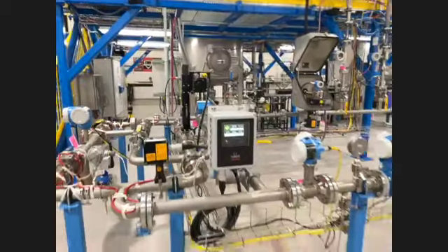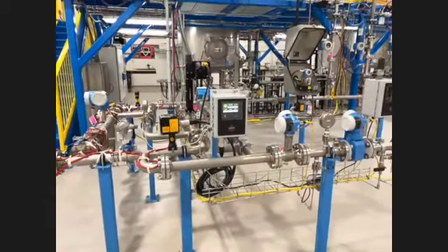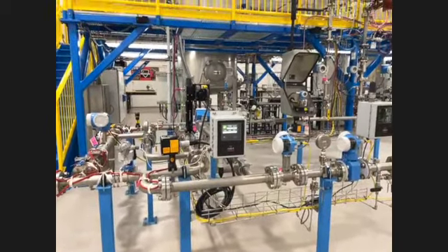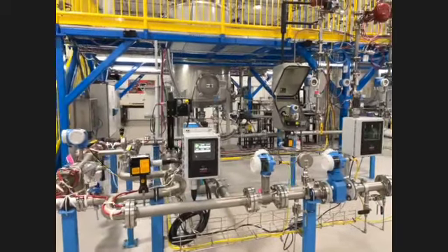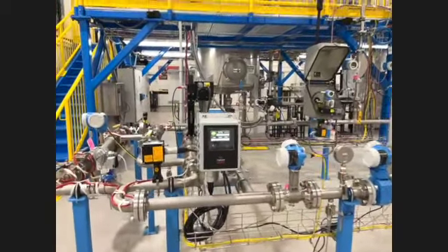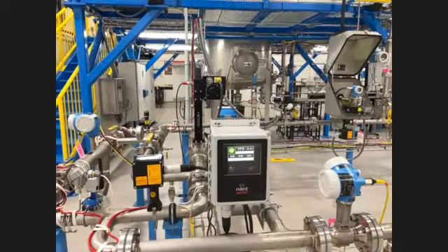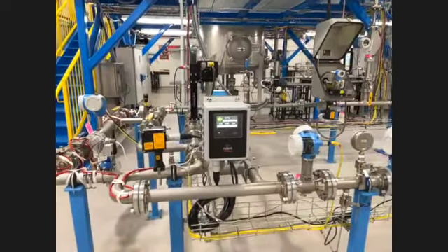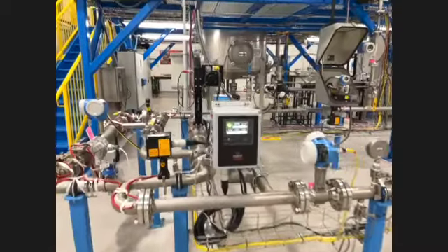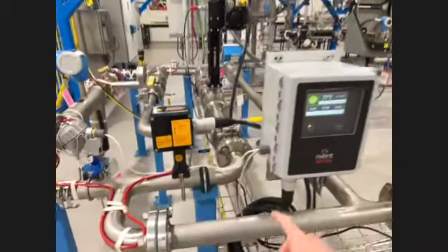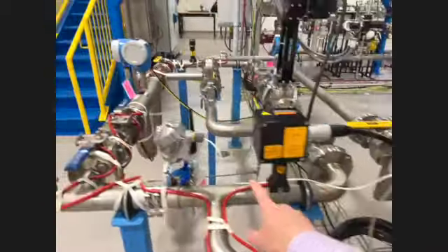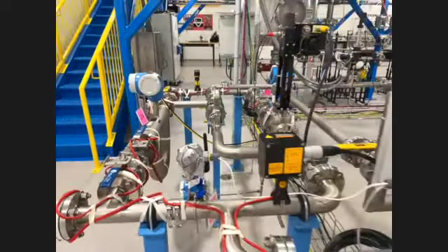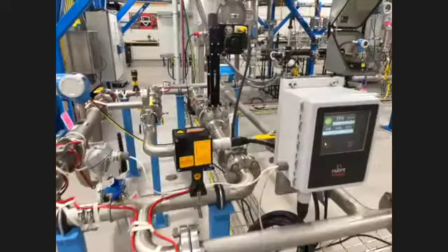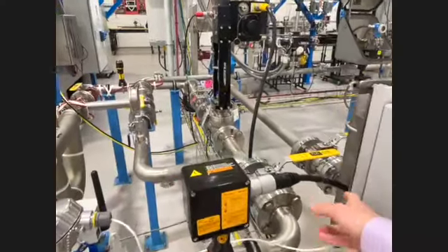So with a heat trace circuit, I'm going to be really fundamental today. If there's any questions that come up, definitely just speak up and I'll address. But the power is coming into this from your general lighting power, any distribution center that you have. Power is coming into this controller, and then we have an RTD coming out right here, sensing the actual pipe temperature. And then power is coming out based on the contactor being closed through this wire here, being fed down through your cable tray over to your power connection kit.